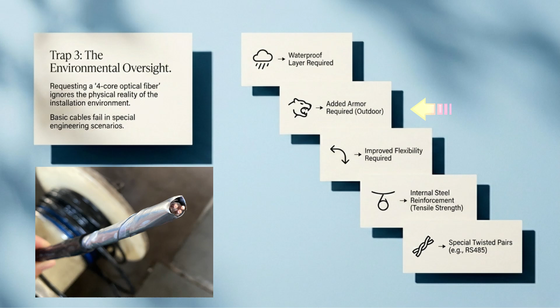The external structure design of the cable needs to be closely integrated with its actual application scenario. For instance, does it need an added waterproof layer? If it is laid outdoors, does it need added armor to prevent animal damage? If it is an environment that requires frequent bending, does the flexibility need to be improved? If it is suspended horizontally, does it need steel reinforcement inside to improve tensile strength?